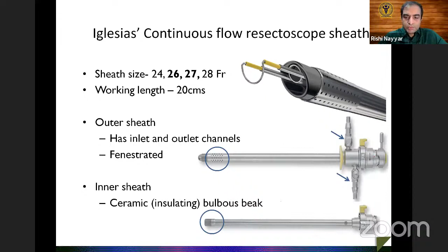that fits inside the outer sheath can be identified by the presence of this ceramic insulation. This is important not only for the insulation, but also for reducing the brightness of the light, which may actually obscure the vision during resection. So this ceramic tip is really important for any resectoscope sheath, and if it is damaged, one should not use that sheath. The inner sheaths are available in two forms.